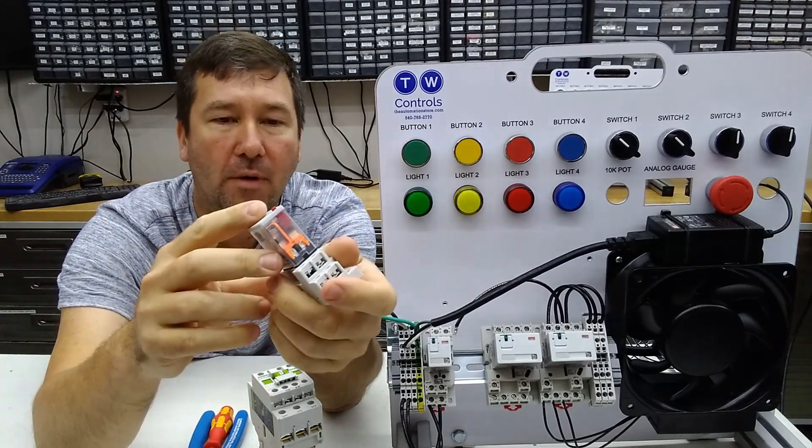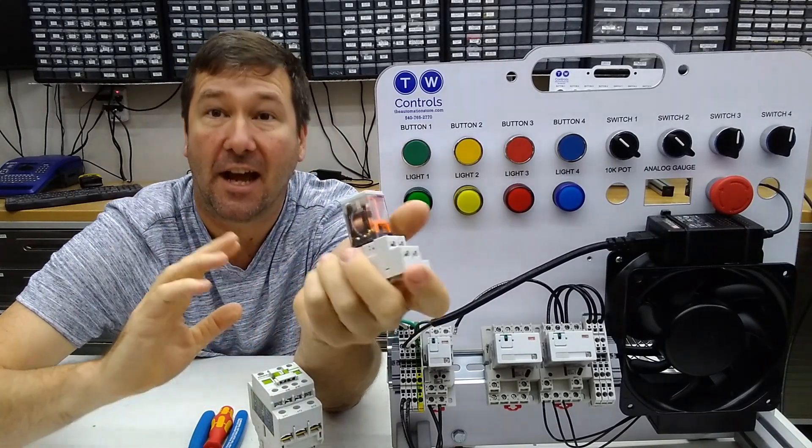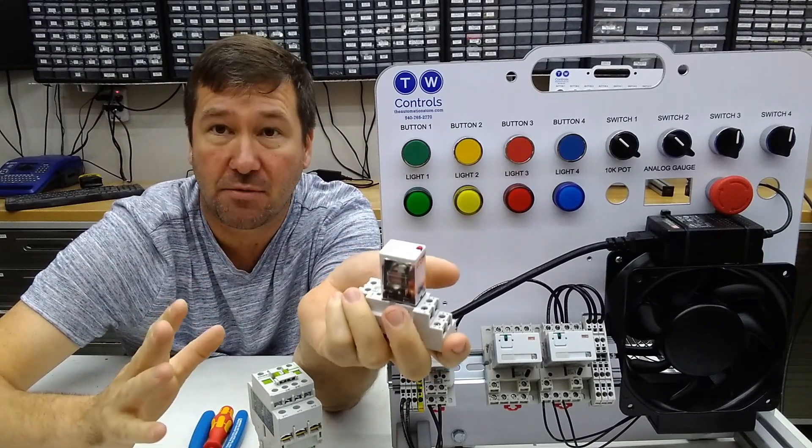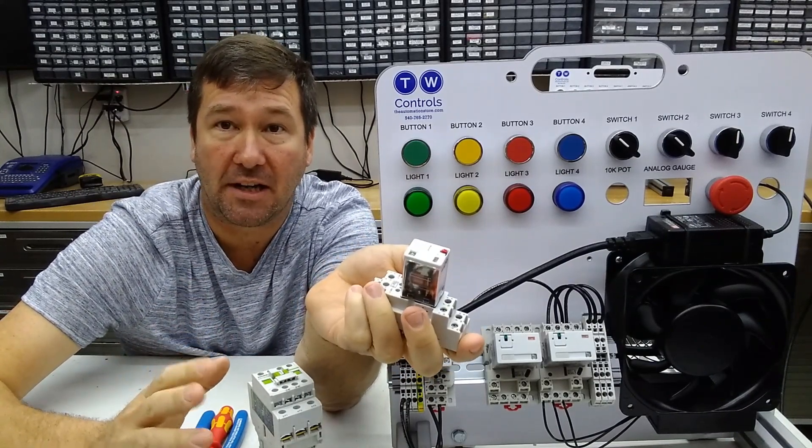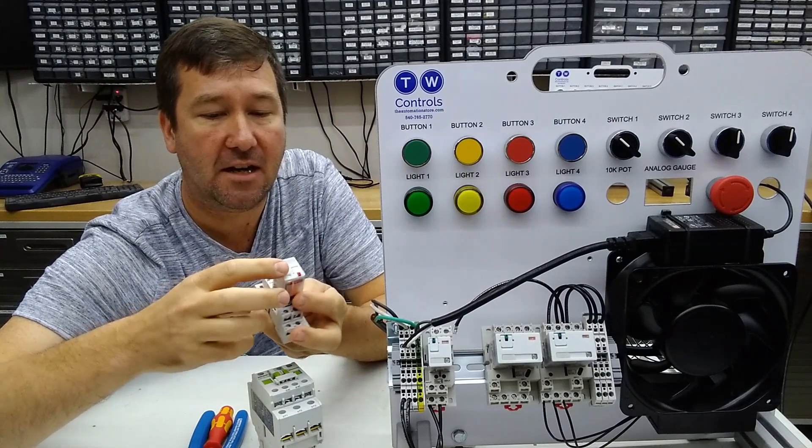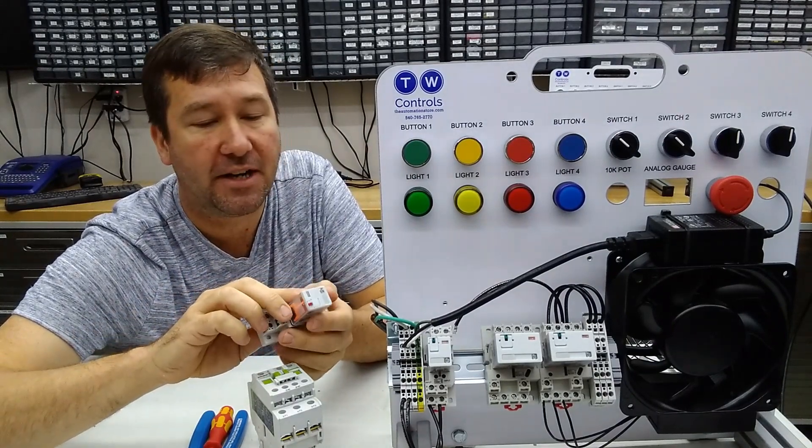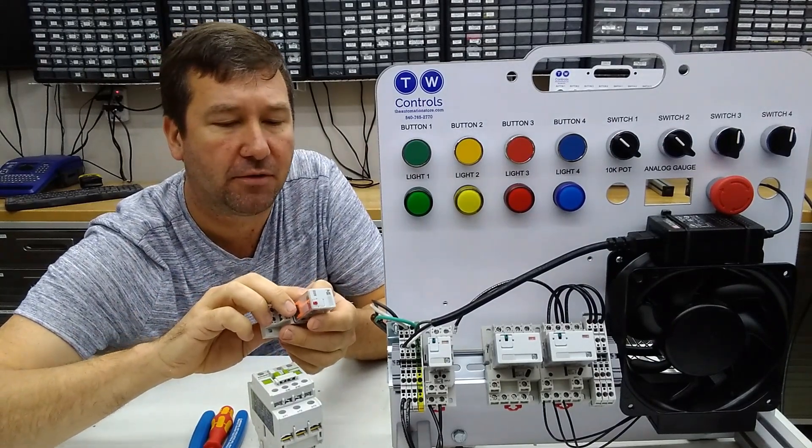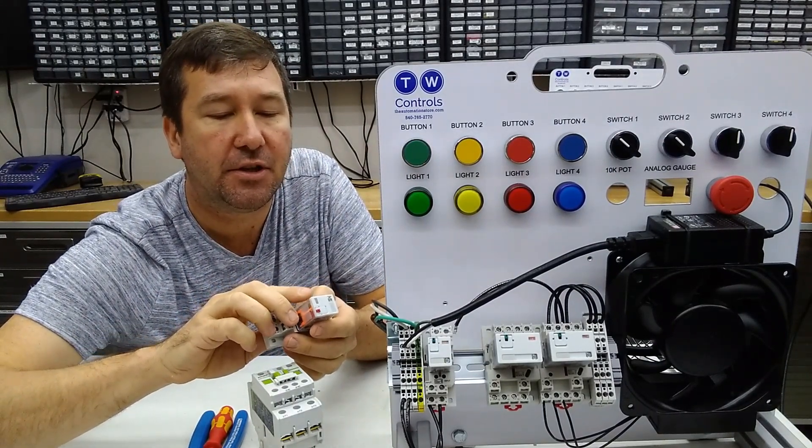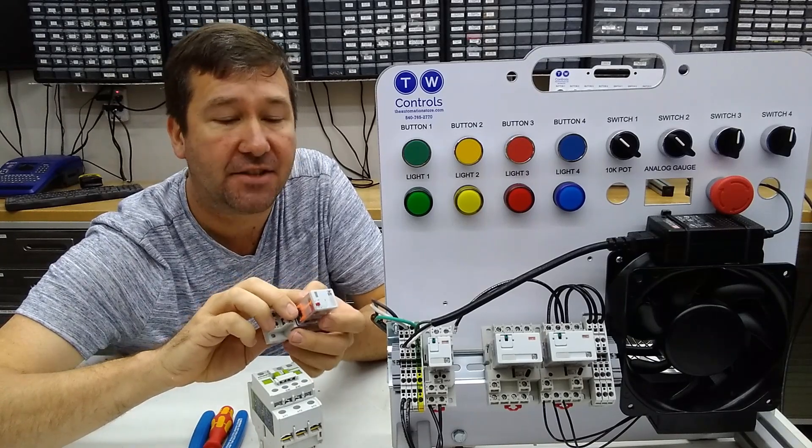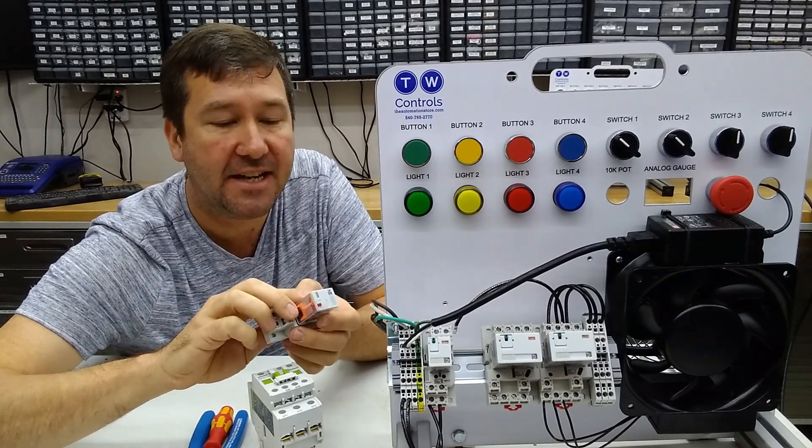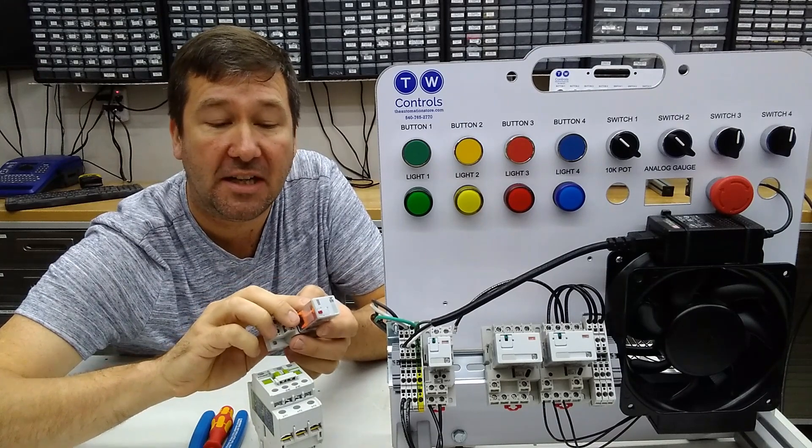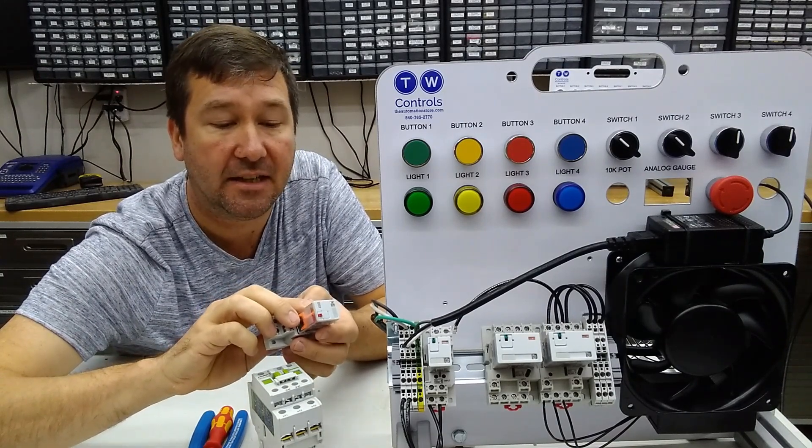All relays and contactors have a contact voltage rating and amperage rating. In the case of this one right here, it has different amperage ratings for different voltages. This one can do 15 amps at 277 volts AC, or it can do 15 amps at 28 volt DC.